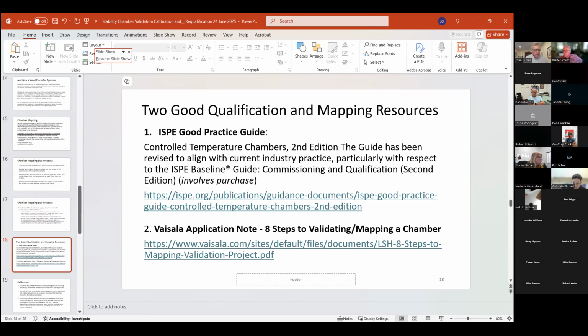Yeah, I can chime in on that one, John. I think it goes exactly to what you said, it depends on the extent of the change. If you feel confident that you can justify that the change was not significant enough to impact the mapping done during the initial validation, then it might be something that could be documented as a justification. If there are questions about whether the change is significant enough, hopefully you could call the manufacturer. We would say, here's the layout of the ductwork in regards to the airflow. Based on what you want to do, we might be able to make a recommendation whether or not a validation would be advisable. A lot of it goes back to your ability to justify it in the event that an auditor is going to ask.